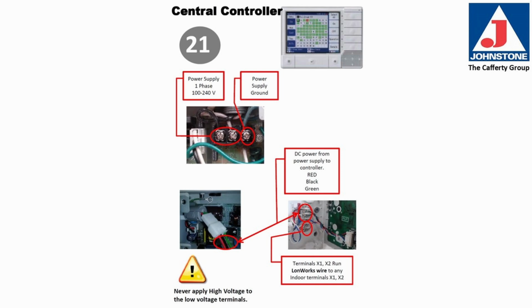Here are the wiring connections for the centralized controller. The power supply, single phase, 100 to 240 volt AC. DC power from the power supply to the controller, red, black, and green wires. Terminals X1 and X2 run LonWorks wire to any of the indoor terminals X1 and X2. Never apply high voltage to low voltage terminals.